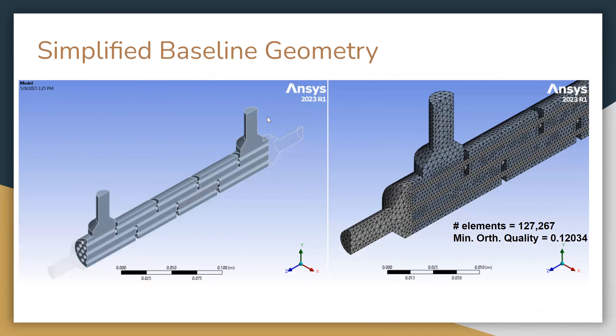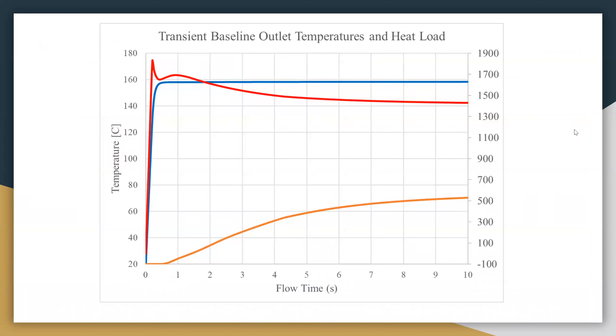Now we're going through the transient results. This is the transient simplified baseline geometry — you can see the basic geometry and the number of mesh elements on the right. The orange outline is the cold outlet temperature, the red outline is the heat load between the warm and cold pipes, and the blue line is the warm outlet temperature. The warm outlet temperature rises very quickly and reaches steady state, while the cold outlet temperature takes quite a while to rise, coinciding with the heat load reaching steady state, at which point the cold outlet temperature begins to rise and then reaches its own steady state.